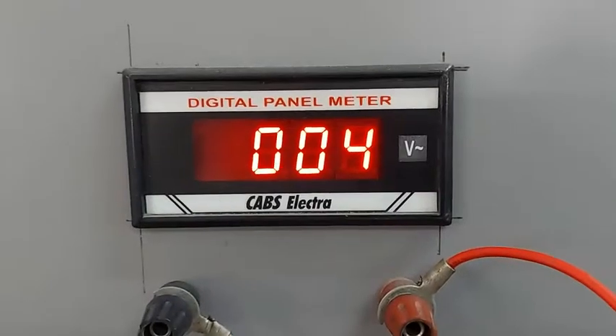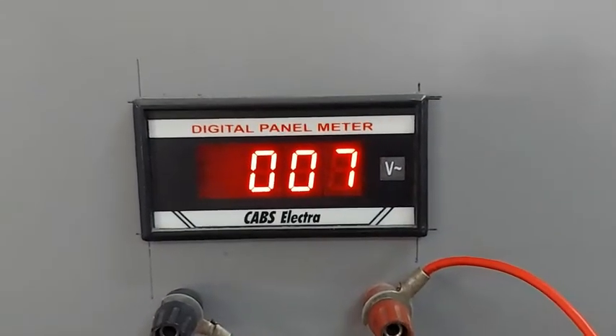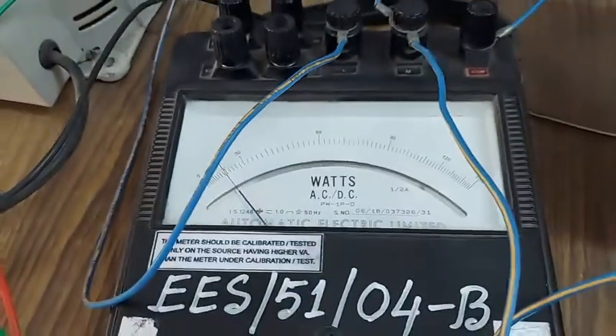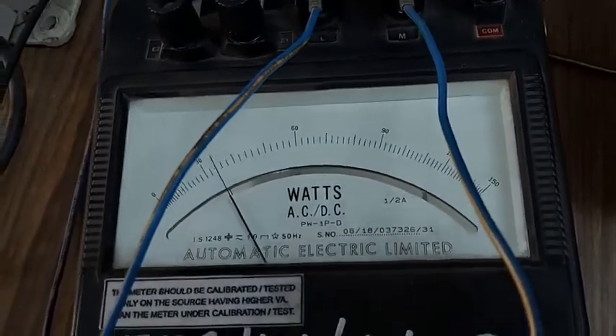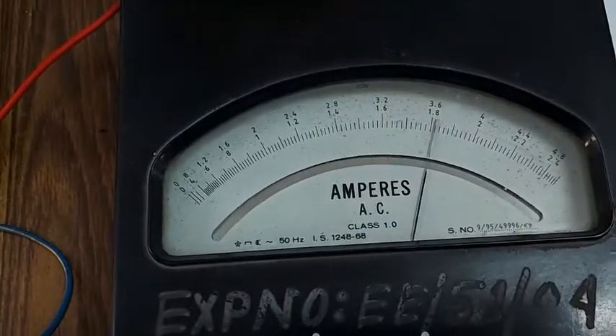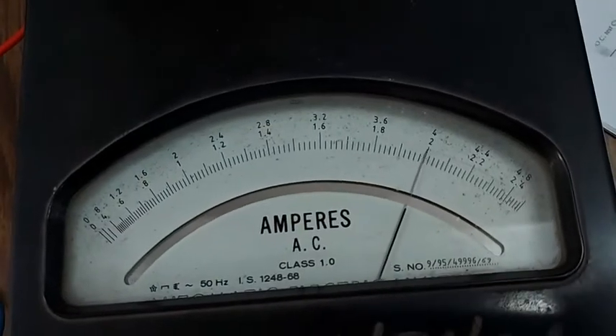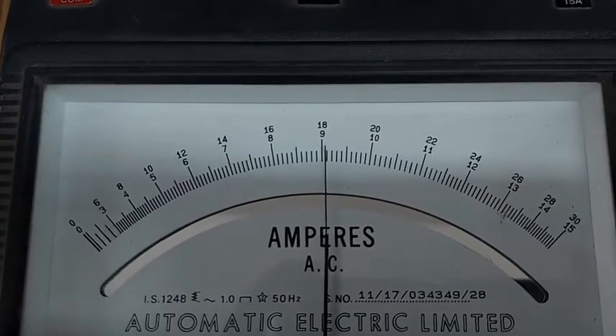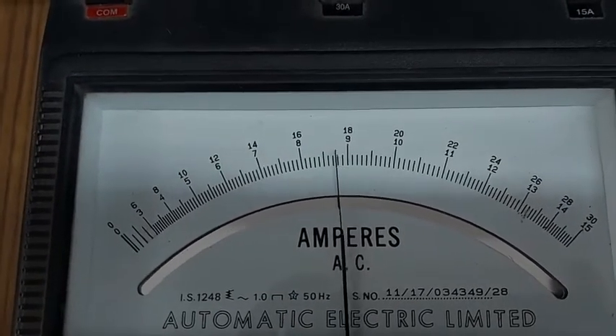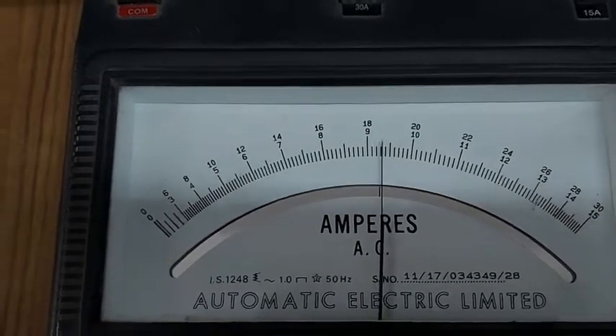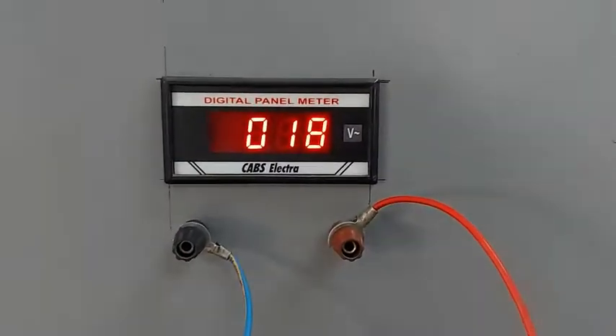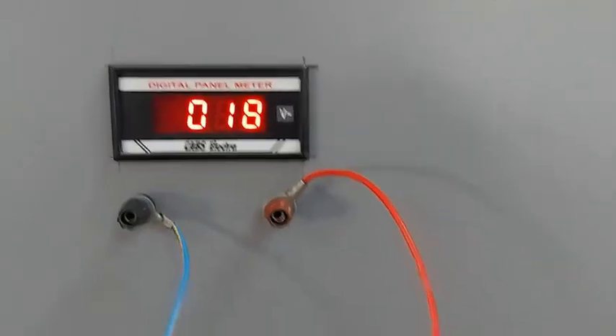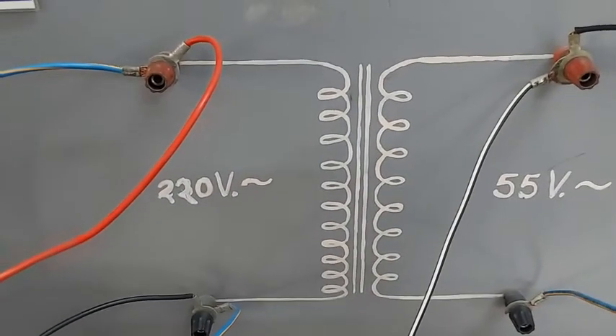So right now the voltage applied to the input is increasing gradually, and you can see that the power is being consumed by the transformer, so power is increasing, and the ammeter, the input current to the primary winding, also is being measured, that is connected to the 5 ampere range, so upper scale will be considered. And in case of the secondary winding also, we are seeing that high value of current is going. So now it has reached 18 ampere, so it is approximately the full load current, and for that full load current the required primary voltage is 18 volt, which is a very less value compared to the full rated value of the primary winding, that is 220 volt winding.